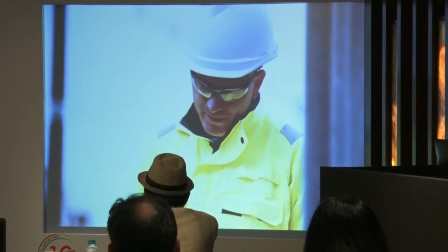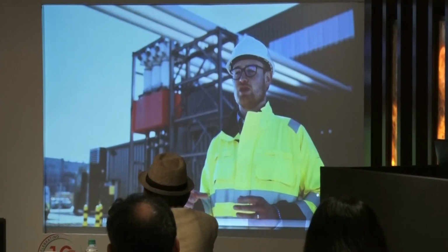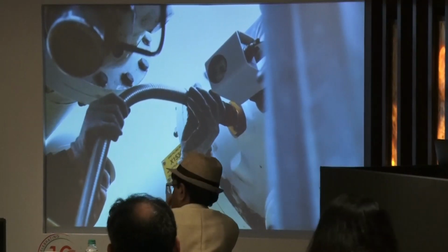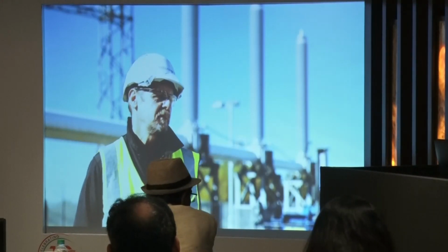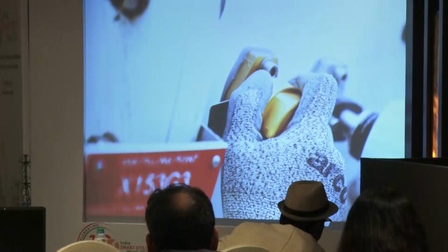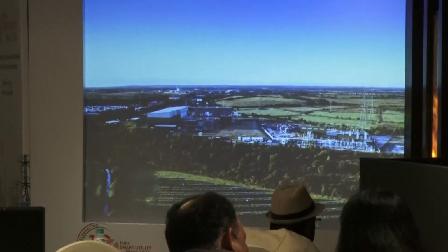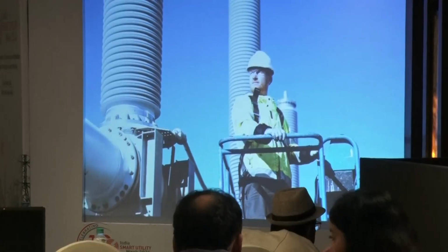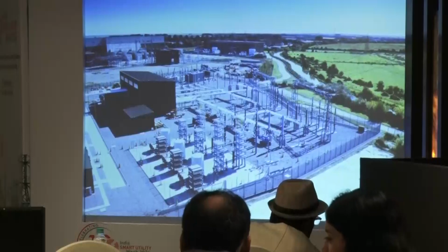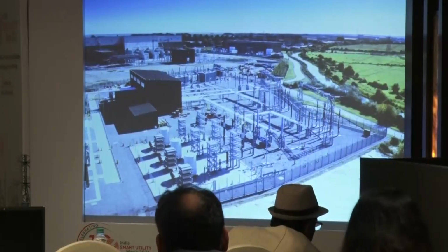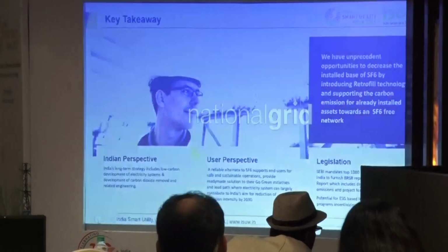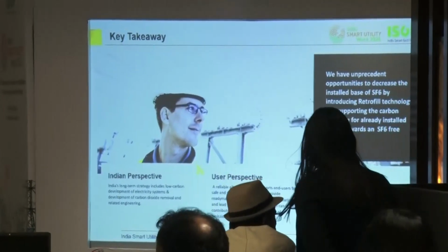The road ahead for Hitachi Energy and National Grid looks like a repetition of this trial throughout the rest of the applicable ELK3 420 fleet within the UK on the National Grid network. Our carbon emissions are dominated by the impact of SF6. So to be able to work on SF6, manage our emissions down, is absolutely key to what we're trying to achieve. In terms of meeting net zero targets, we have made a commitment to reduce our SF6 emissions to the environment by 50% by 2030. We've also set ourselves the ambition of completely removing SF6 from our operations by 2050.